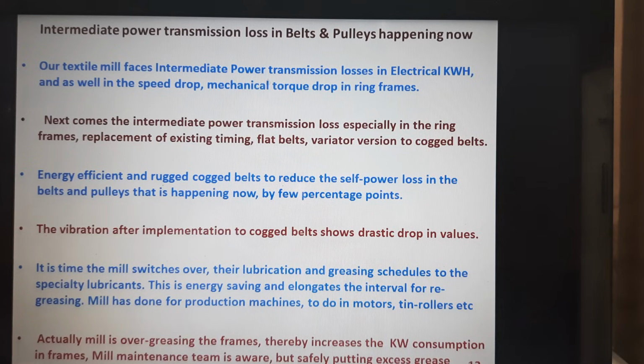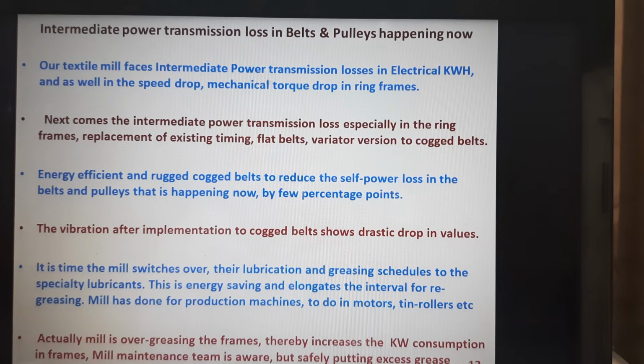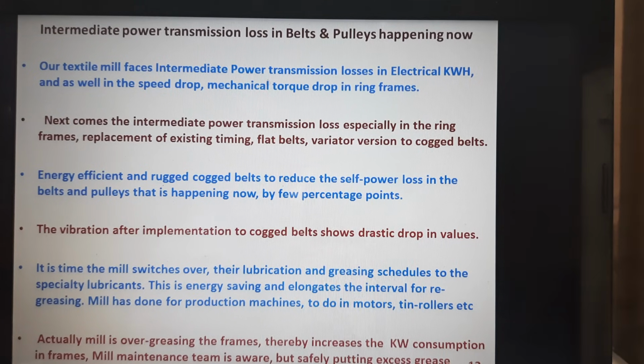Coming to the intermediate power transmission losses in belts and pulleys that is happening now. The mills are concentrating on the electrical input kWh only, or the speed drop or the mechanical torque drop in the ring frames. But what we have observed for the past 3 or 4 years is that the existing flat belts or the timing belts or the variator versions are consuming more because of their self consumption.